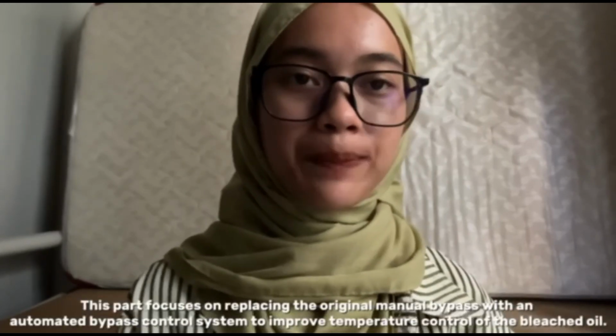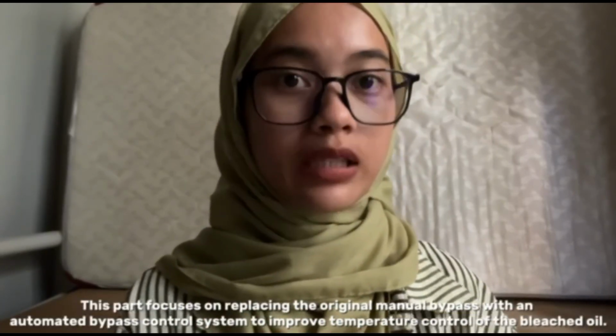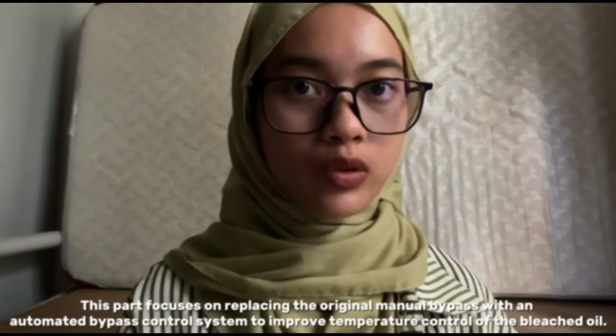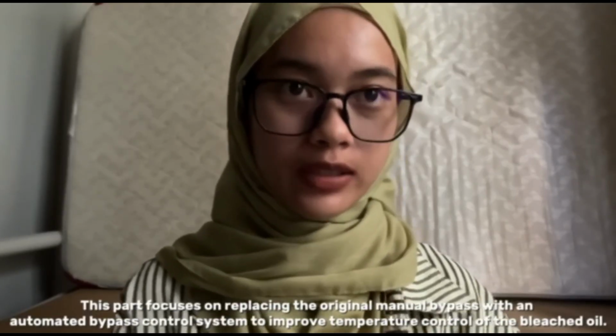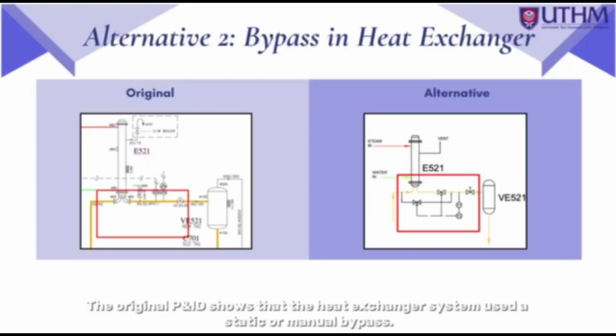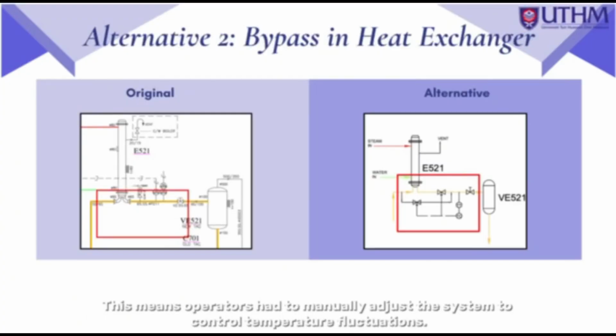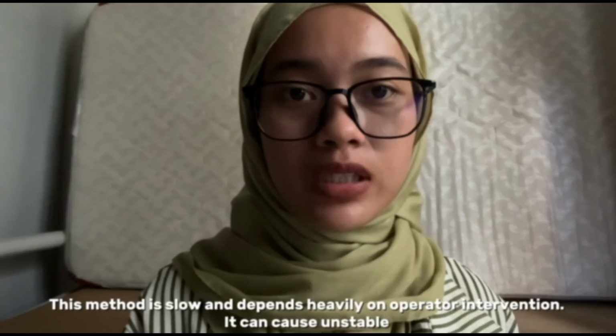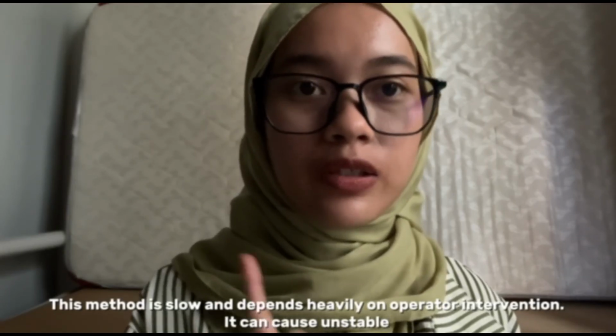This part focuses on replacing the original manual bypass with an automatic bypass control system to improve temperature control of the bleach oil. From this slide, the original P&ID shows the heat exchanger system used a static or manual bypass. This means operators had to manually adjust the system to control temperature fluctuation. This method is slow and depends heavily on operator intervention.